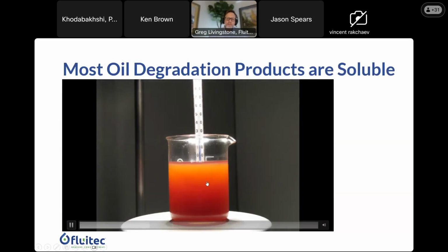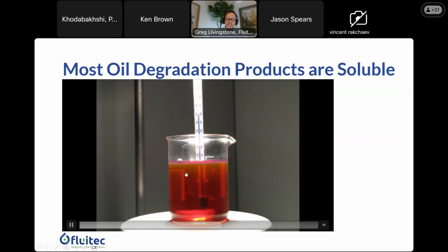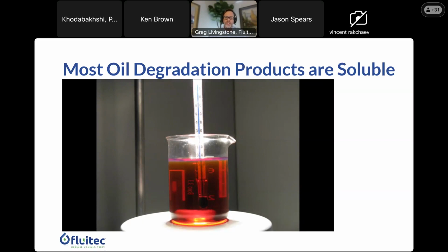The whole video has been sped up, and as you can see, the temperature starts to increase here. At about 40 degrees C, you'll see all of these things start to go into solution. So it suggests that the melting point, or the point where these products transition into solution, is around 40 degrees. And how many systems are operating at 40 degrees?